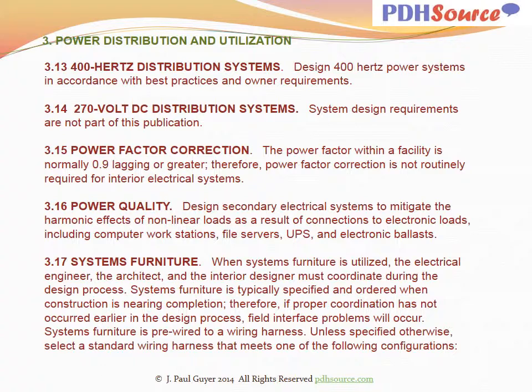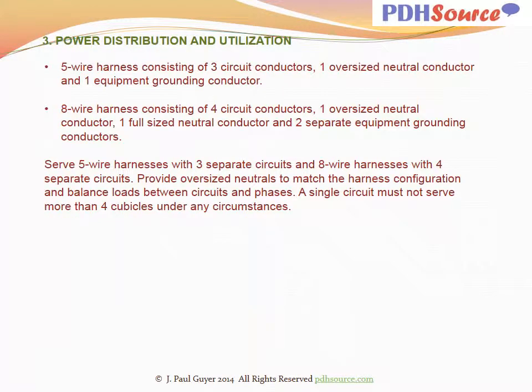Unless specified otherwise, select a standard wiring harness that meets one of the following configurations. 5-wire harness consisting of 3 circuit conductors, 1 oversized neutral conductor, and 1 equipment grounding conductor. 8-wire harness consisting of 4 circuit conductors, 1 oversized neutral conductor, 1 full-size neutral conductor, and 2 separate equipment grounding conductors. Serve 5-wire harnesses with 3 separate circuits and 8-wire harnesses with 4 separate circuits. Provide oversized neutrals to match the harness configuration and balance loads between circuits and phases. A single circuit shall not serve more than 4 cubicles under any circumstances.